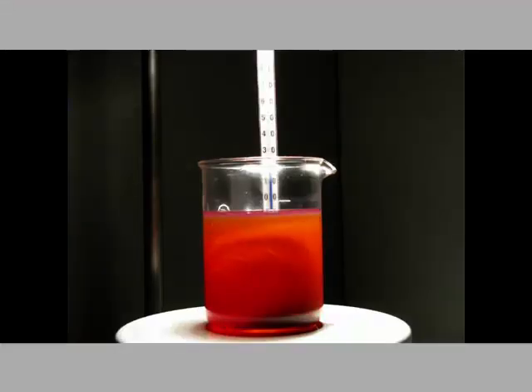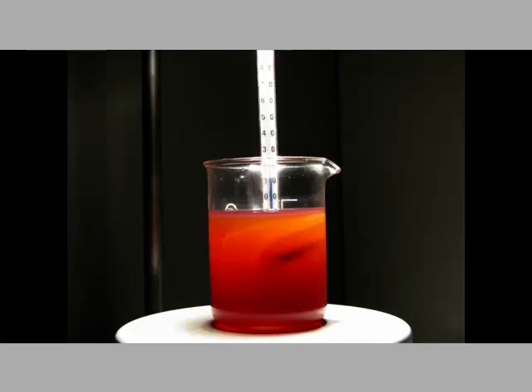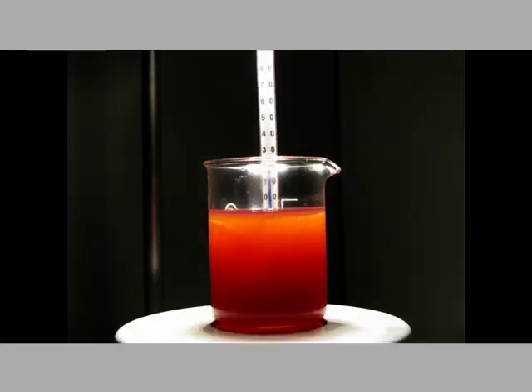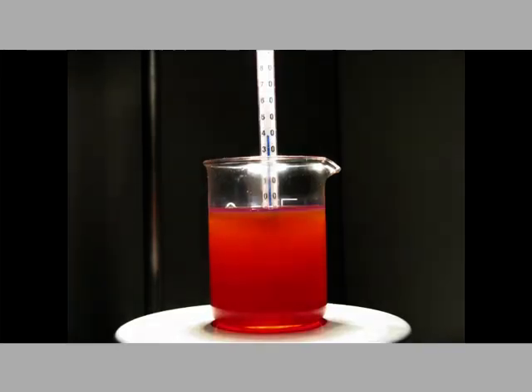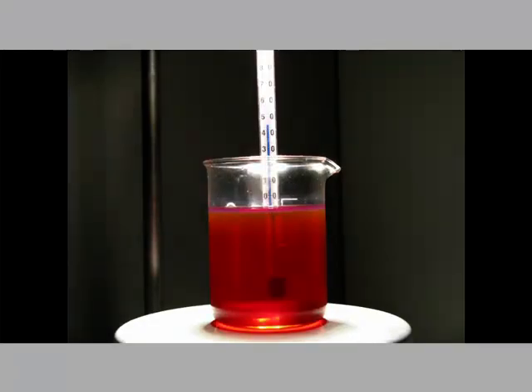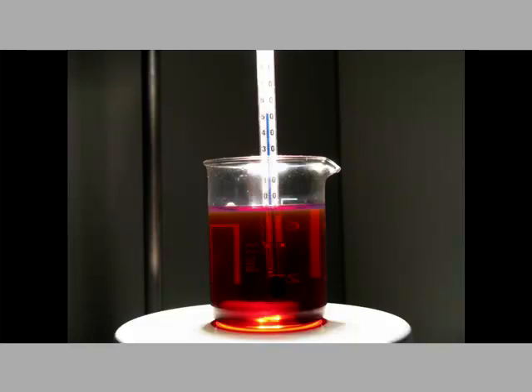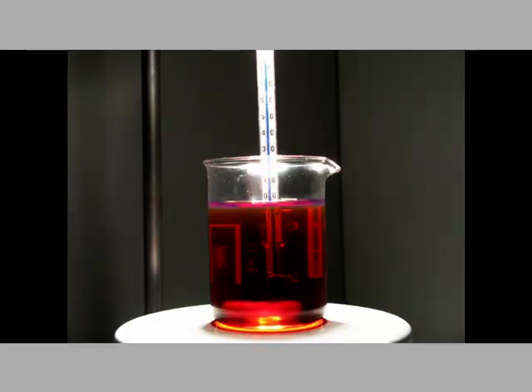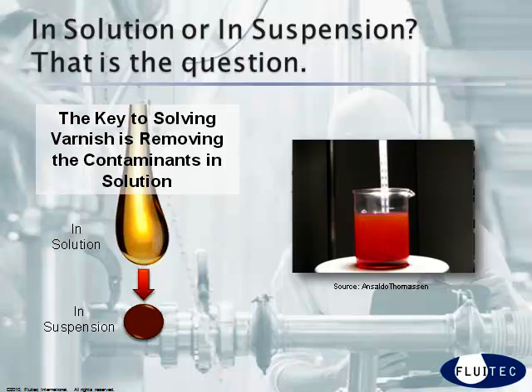This video shows an image of heavily oxidized turbine oil. Notice how cloudy it is. These contaminants have agglomerated together and have become so large that they are obscuring light and creating the haze. Now, watch the thermometer behind the fluid. As the fluid approaches 40 degrees Celsius, it starts to clear up. Once the fluid hits 55 degrees Celsius, it is perfectly clear. This is, in fact, the most important aspect of selecting a technology to solve varnish.